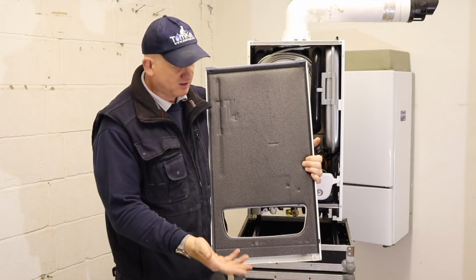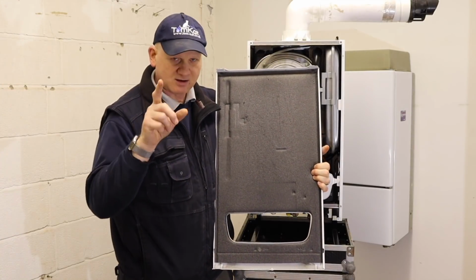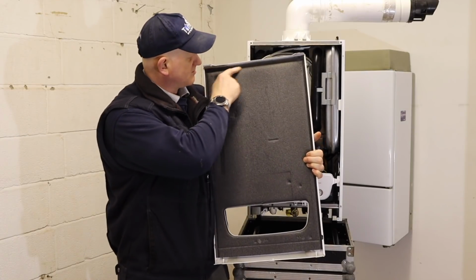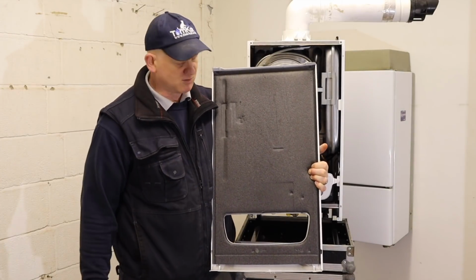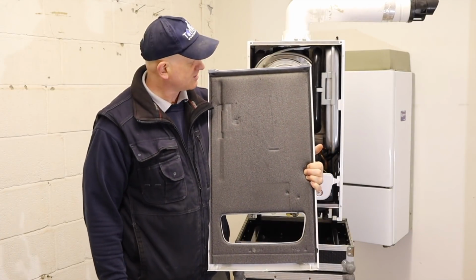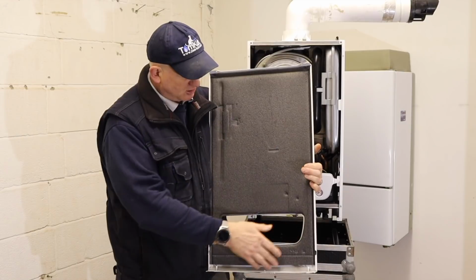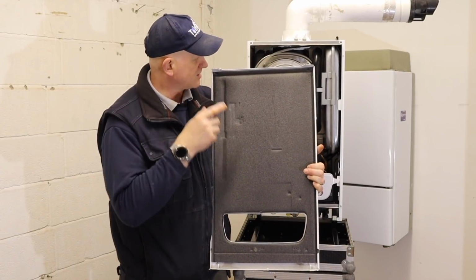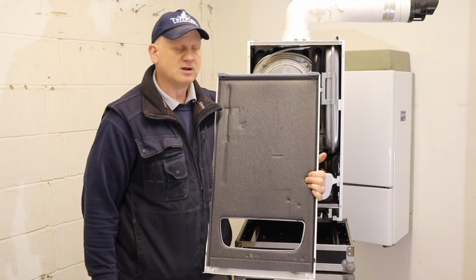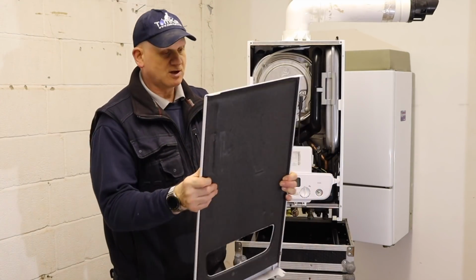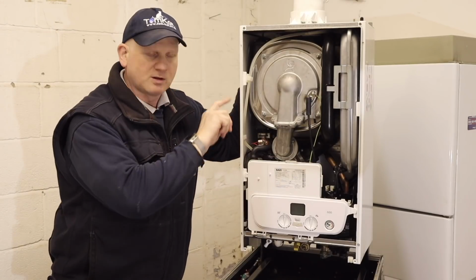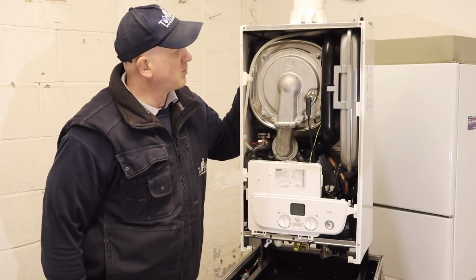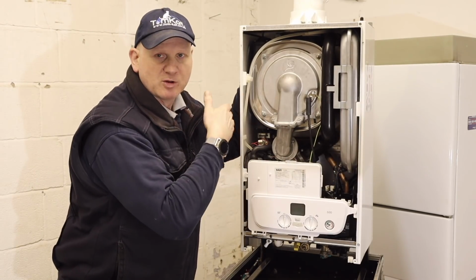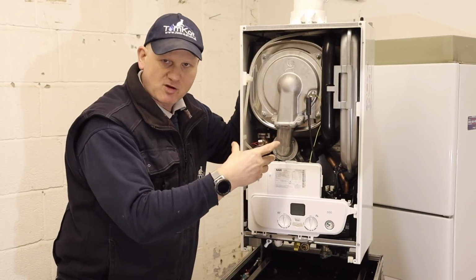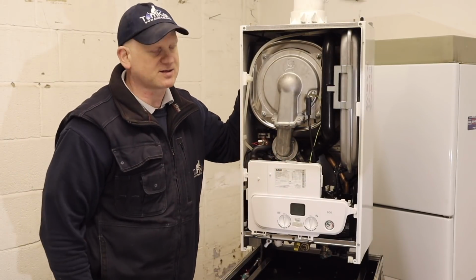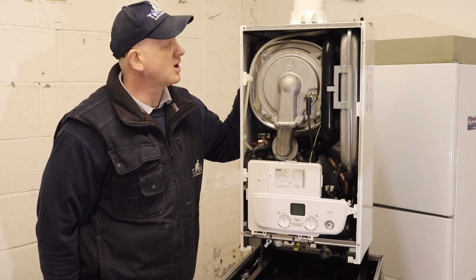this front cover. Now if this was missing or broken, under the new IGEM G11, this would be at risk, and obviously if we had products of combustion coming out, it would be immediately dangerous. So always inspect this seal to make sure it's still here, because it serves as the seal for the combustion chamber. So, front cover. Also, the sides are removable on this boiler. So both sides are removable. So if you're struggling to get access through the front, then you can actually take the sides off, and there's just 3 screws holding it together.